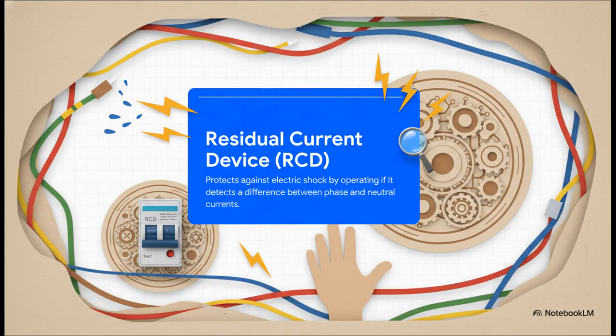For that, you need a specialist. And that specialist is the residual current device, or RCD. Its entire reason for existing is to do the one thing an MCB can't: detect those tiny, dangerous trickles of current that mean someone is getting an electric shock, and shut the power down now.